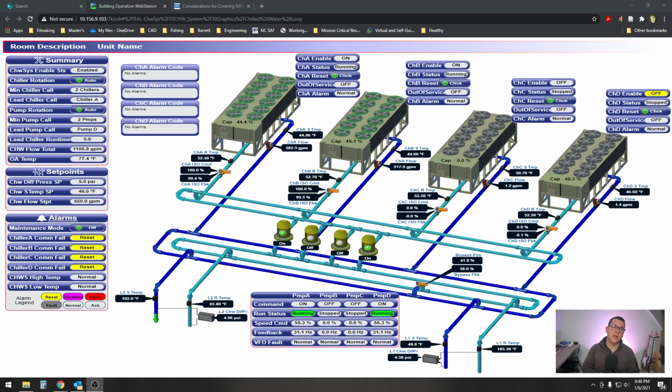So the three things, in the simplest terms, that describe how this system works are pumps, or flow through the system, the minimum flow over the chillers by themselves, and the temperature of the supply water. So we're boiling this entire complex system down into those three things, and then what actually controls those three variables, and how we accomplish meeting those criteria.